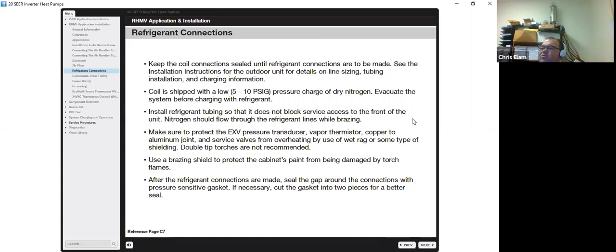It is important that nitrogen be flowed through the refrigerant lines while you're brazing. They have many different options to do that now. You have small adapters, and several of the nitrogen gauges have it built in for a purge cycle. That will keep your refrigerant system clean. These are top-notch systems. If they're improperly put in, you can guarantee yourself some serious problems within the system.